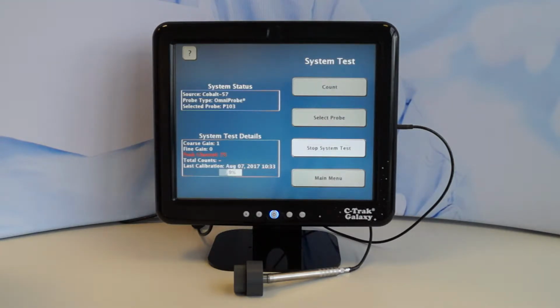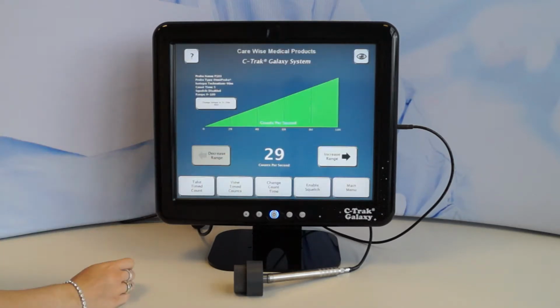Please note that the source used for calibration needs replacing every 18 months as it decays over time. If any errors occur during calibration, please refer to the manual's troubleshooting and error messages section for further information. Once calibration is complete, press the Count button to return to the main screen and use the system.